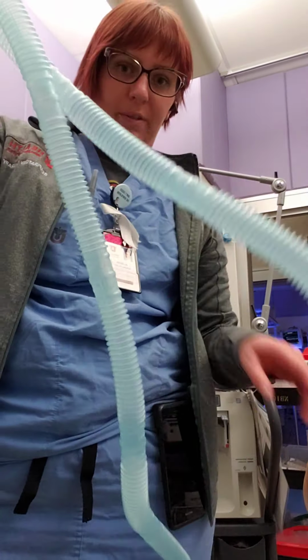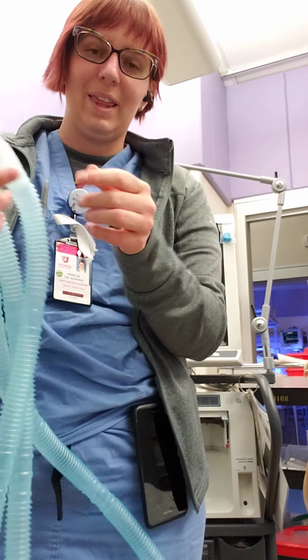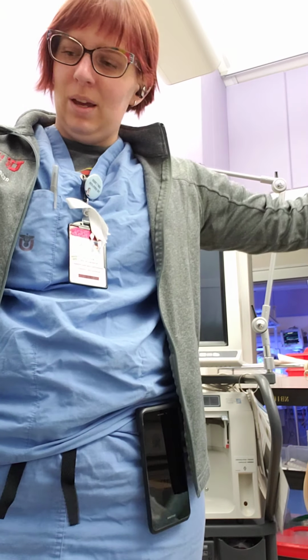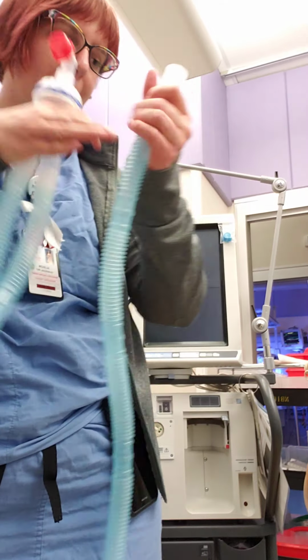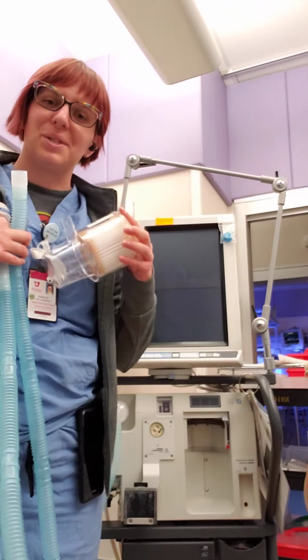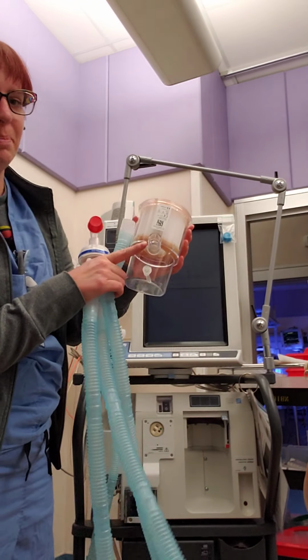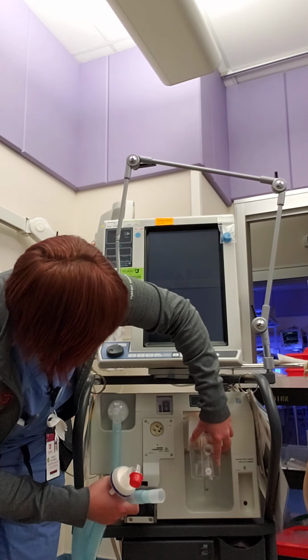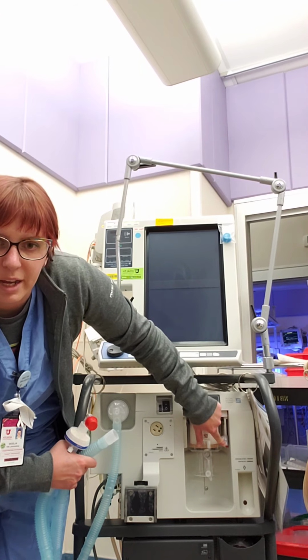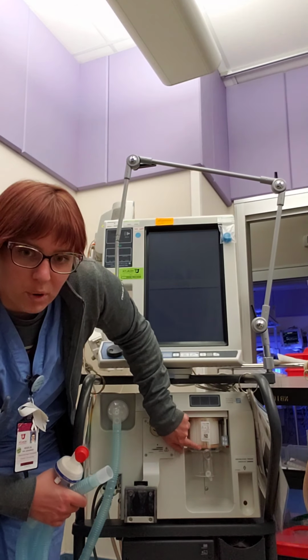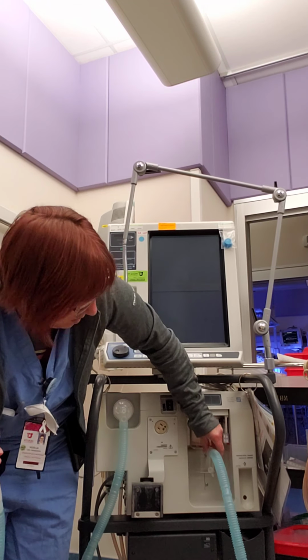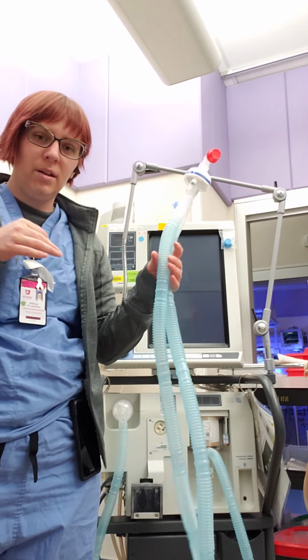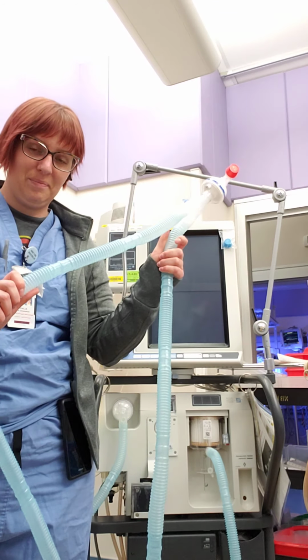Next we go to our expiratory filter, which when we go to the humidified, it'll be a little easier to see. Our expiratory filter, we take our expiratory limb, we take our expiratory filter. You go so that this part is pointing out. There's grooves right up here on the top. You slide it in, and then you lock it with this little limb that locks. After that, you take the big port right here, and stick it on. Okay, that's how you set up the circuit for a non-heated ventilator.